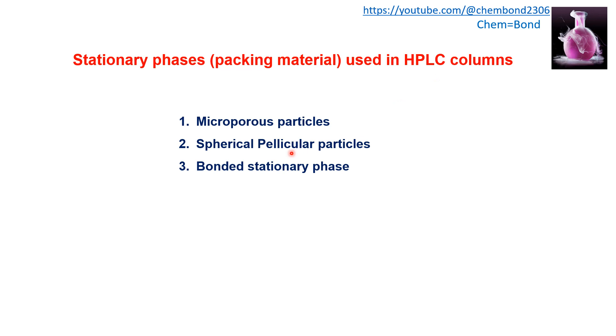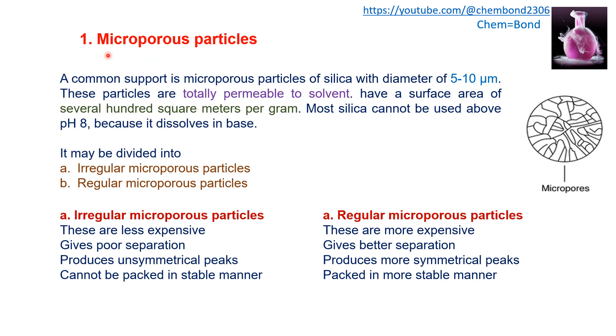Stationary phase or packing materials used in HPLC columns include microporous particles, spherical pellicular particles, and bonded stationary phases. The most common support is microporous particles of silica with a diameter of 5 to 10 micrometers. These particles are totally permeable to solvents and have a surface area of several hundred square meters per gram. Silica cannot be used above pH 8 because it dissolves in base — this is a drawback of silica microporous particles, though they remain the most commonly used packing material in HPLC.